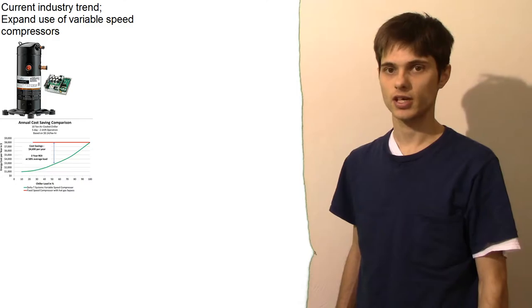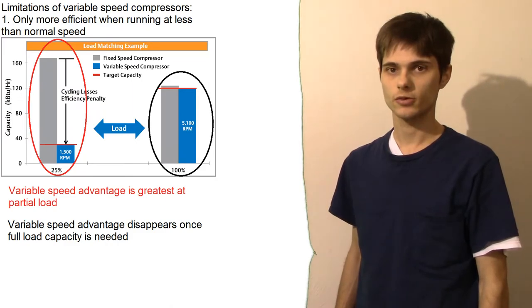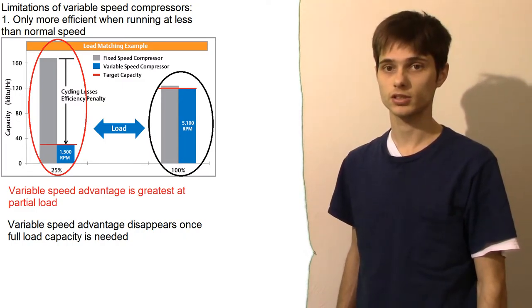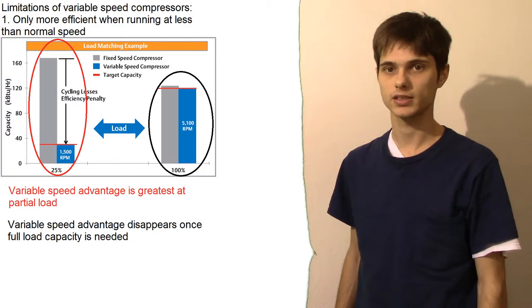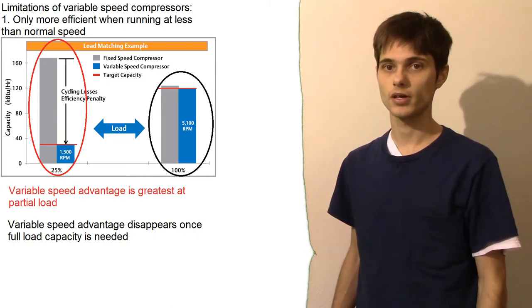However, variable speed technology is not without its limitations. Primarily, the limitation is the compression only becomes more efficient when the compressor is operating at less than its normally rated speed. Which is okay in most situations because in most situations full capacity isn't needed all the time. So the compressor speed can be reduced and the efficiency can go up most of the time, but not all times.